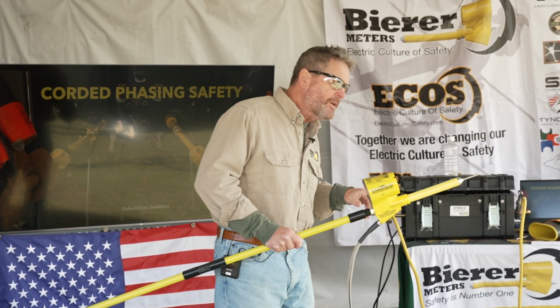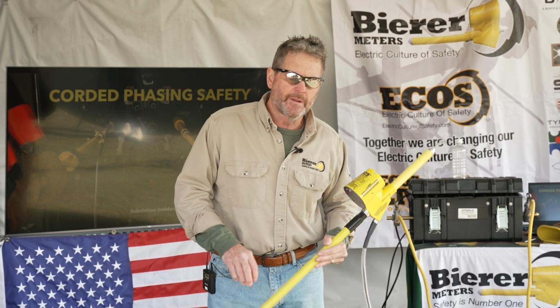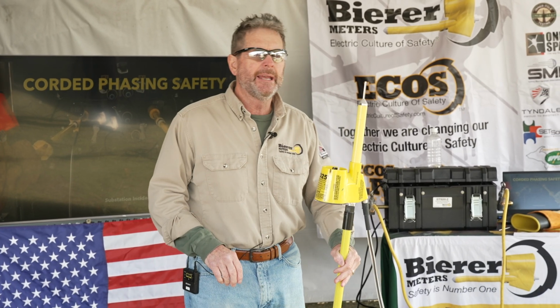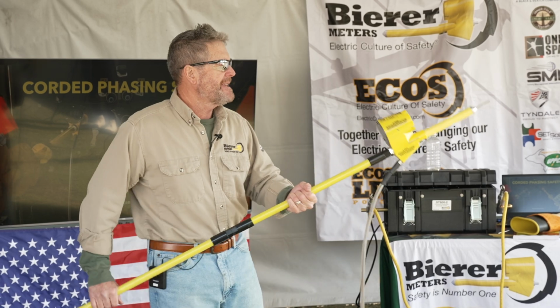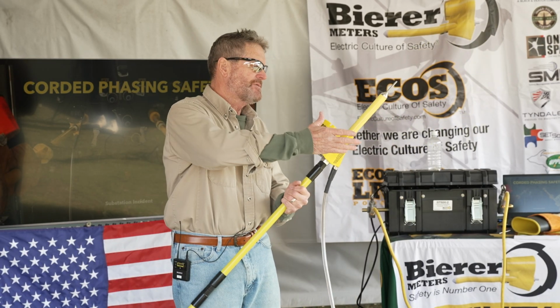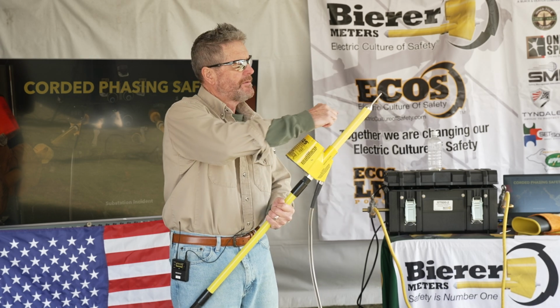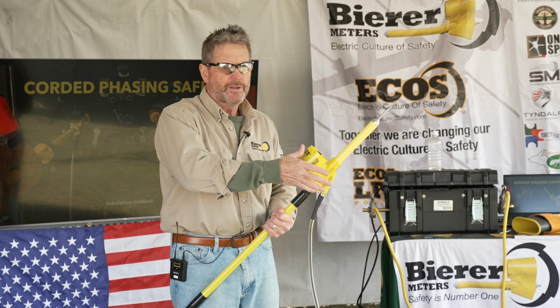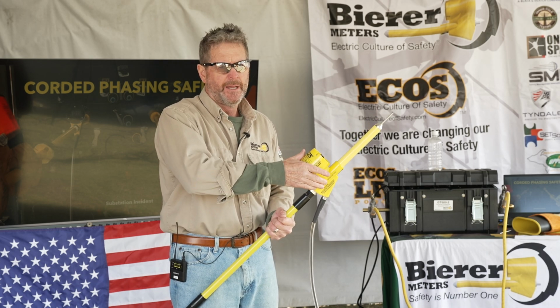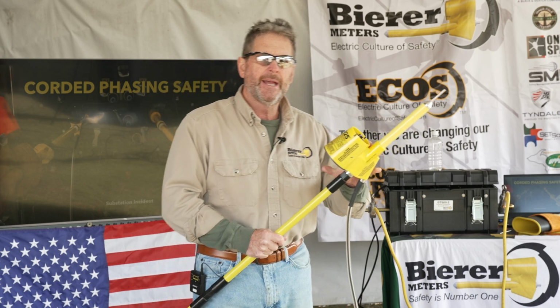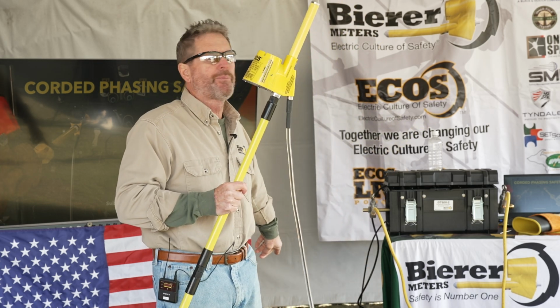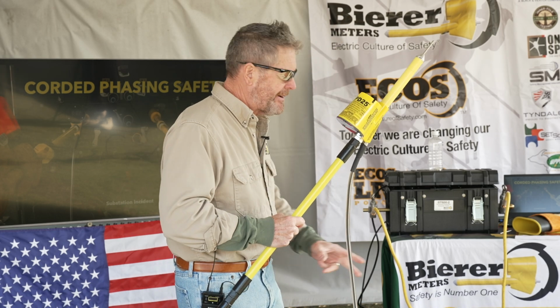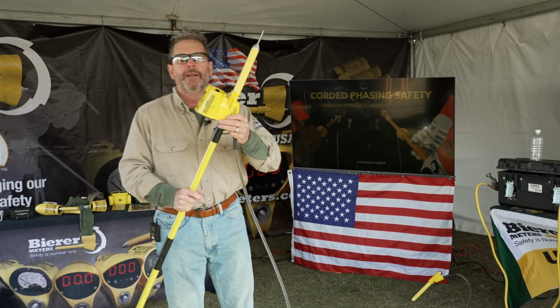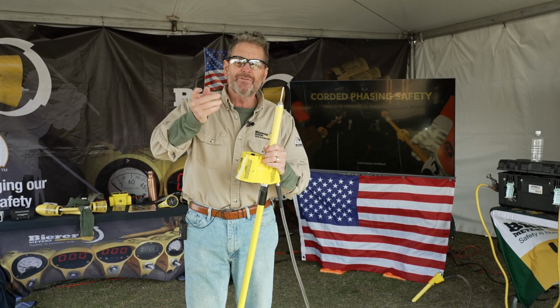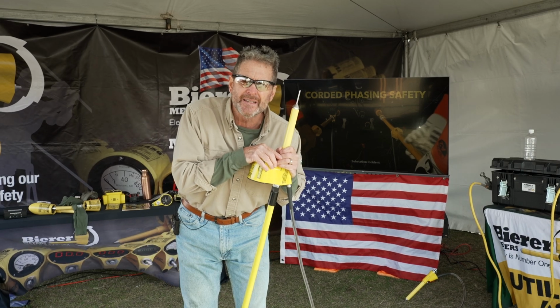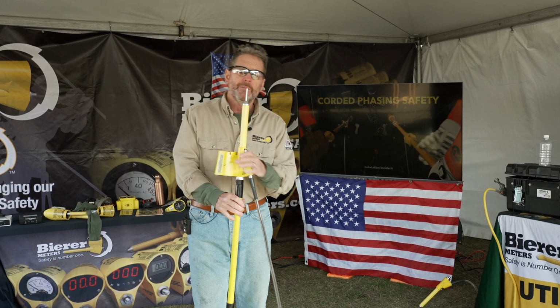So we got a call from this utility, and what happened was the linemen were in a substation and made contact with a hot phase at full primary potential. There are resistors here, but no resistors between that hot phase and the meter head - full potential. It popped that meter head, flowed down the cord to that secondary probe, and it blew up at the secondary probe and at the meter head. The tool, when it all came down afterwards, actually functioned after this. I couldn't believe it - we had to clean it up a little, but it actually worked.